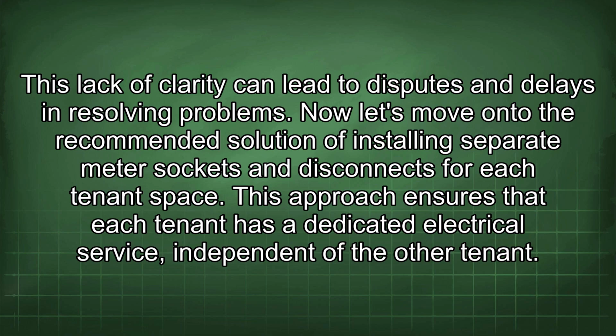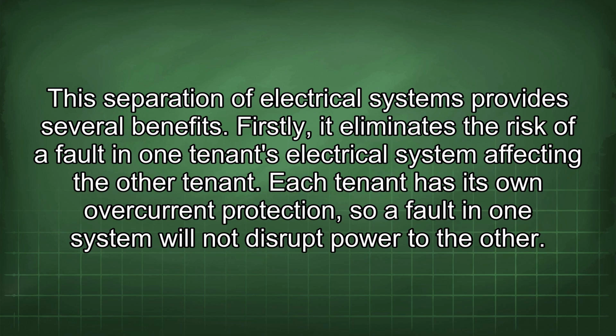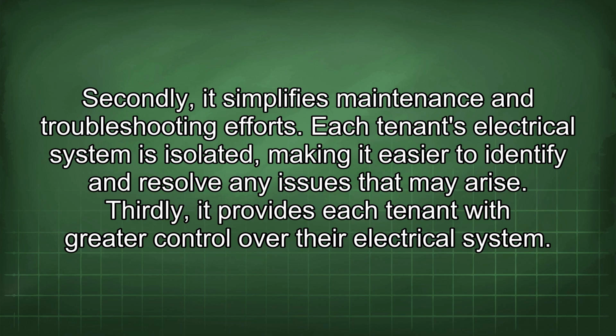Now let's move on to the recommended solution of installing separate meter sockets and disconnects for each tenant space. This approach ensures that each tenant has a dedicated electrical service independent of the other tenant. This separation of electrical systems provides several benefits. Firstly, it eliminates the risk of a fault in one tenant's electrical system affecting the other tenant. Each tenant has its own overcurrent protection, so a fault in one system will not disrupt power to the other. Secondly, it simplifies maintenance and troubleshooting efforts. Each tenant's electrical system is isolated, making it easier to identify and resolve any issues that may arise.